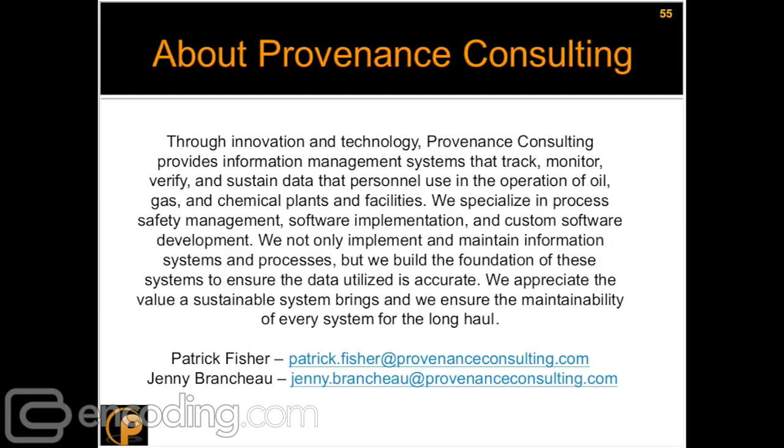We have a bunch of questions, and if anyone has any more, please use the chat box and send to host. First question, are alarms normally considered IPLs? I didn't think so. That's a great question. I've been using the term alarm throughout this, but what I actually meant was alarm with operator action. An alarm by itself is not an IPL. You need to be able to act on it, so an operator needs to be able to act on it. In that case, they can be considered IPLs if you've documented that both the alarm and the action that the operator takes are independent and effective. And there's more information on that in even the purple LOPA book.